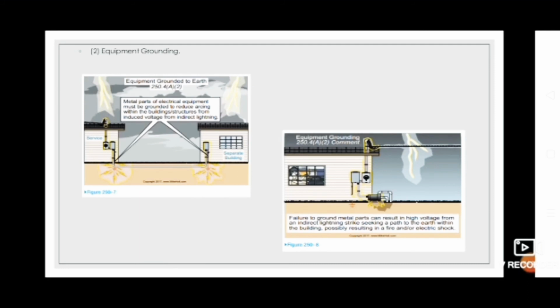Second, equipment grounding. Metal parts of electrical equipment are grounded to reduce voltage induced within the building or structure from an indirect lightning strike. Failure to ground metal parts to the earth can result in voltage being induced on the metal parts from an indirect lightning strike, seeking a path to the earth within the building, possibly resulting in a fire and/or electric shock from the side flash.